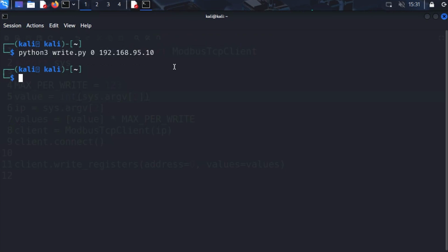One possibility of why nothing is happening is because we only wrote the registers once, and the registers are quickly being overwritten by the PLC. Every cycle, the PLC is probably calculating the correct value to set the valve position to and sending that value, possibly many times per second. So us setting it to a different value one time probably won't make any lasting changes.